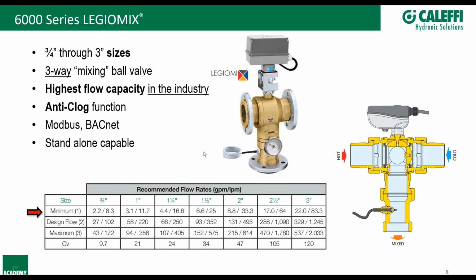Sure. So again, with a power outage, for whatever reason, the actuator is a 24-volt floating control actuator, so it's going to fail in place, wherever that happens to be. Now if it's something you wanted to bypass for whatever reason, you can remove the actuator, and there's actually a slotted screw in the top of the valve stem so you can operate the valve manually if you really wanted to.